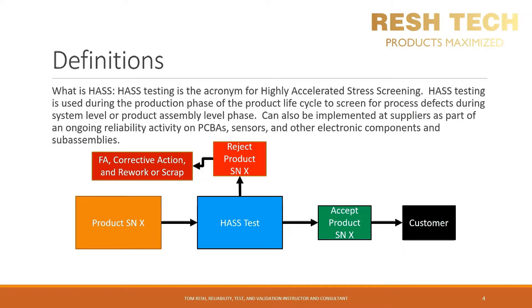Let's go ahead and define HASS. What is HASS? HASS is Highly Accelerated Stress Screening. HASS testing is used during the production phase of the product life cycle to screen for process defects during system level or product assembly level phase. It can also be implemented at suppliers as part of an ongoing reliability activity on PCBs, sensors, and other electronic components and sub-assemblies. For products that are too large to apply this type of testing, you can implement HASS into your supplier ongoing reliability testing for your components and sub-assemblies. Below is a high-level process that shows how HASS is integrated into a production process to weed out defective parts, workmanship issues, and manufacturing equipment-induced process issues.